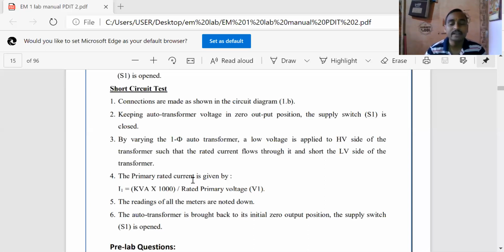Keep in mind, don't apply 230 volt while doing the short circuit test. If you apply 230 volt, the transformer will be damaged. You need to apply rated current under the short circuit test, not rated voltage. The rated current is 8.6 ampere, so you go by the ammeter reading. You put your multifunction meter in the current range, so that is the ammeter. Then slowly vary the variac or auto transformer. Only about 15% voltage you have to apply. 8.6 is the maximum, so up to 8.6 ampere you need to vary the variac.